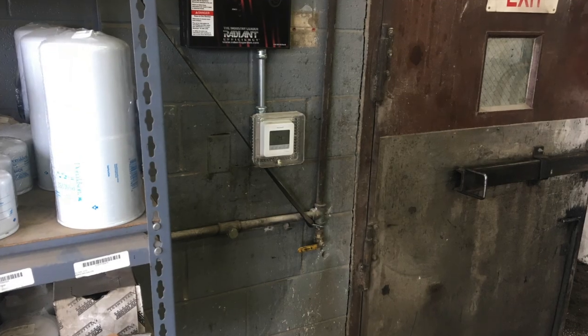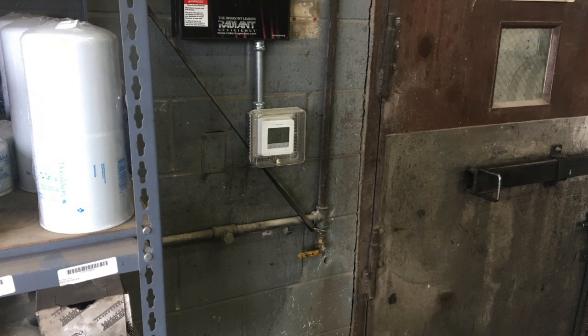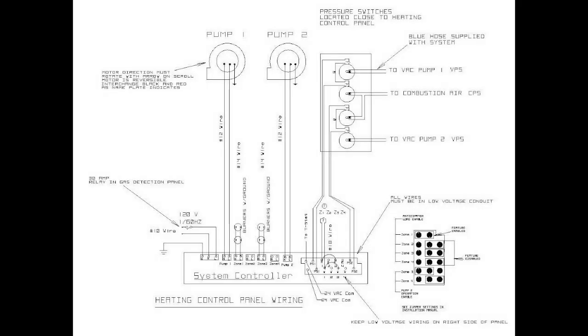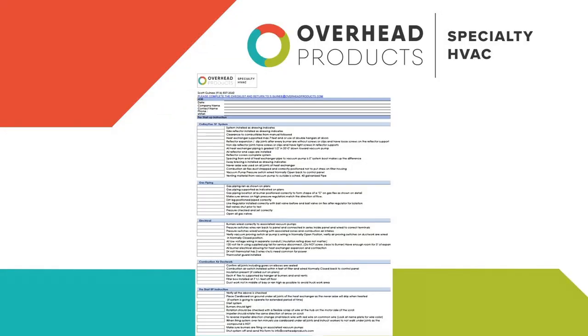All thermostat wiring must be in separate conduit, no matter what wire insulation is used. This control panel is very susceptible to AC induction on the low voltage side, causing major issues requiring new wiring to stats. You're now ready to go through the installation checklist provided in the submittal.